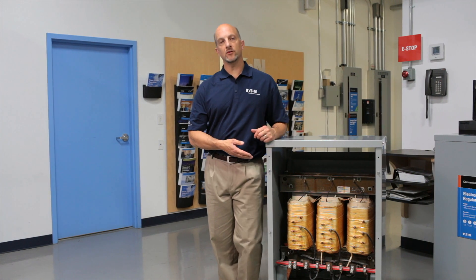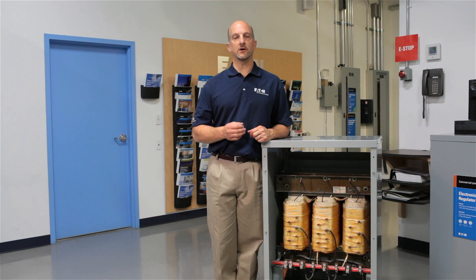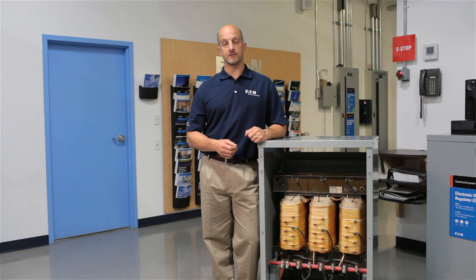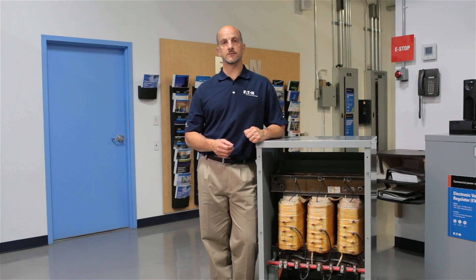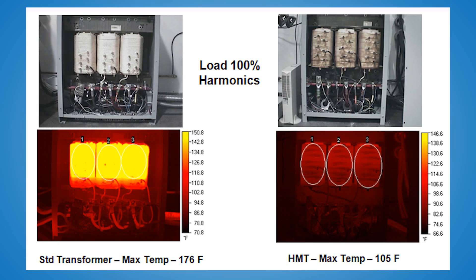Overheating of equipment is a very common result of harmonics. In commercial applications, harmonic current causes the transformer's core and windings to overheat. Over time, this will progressively damage the transformer, resulting in premature failure.